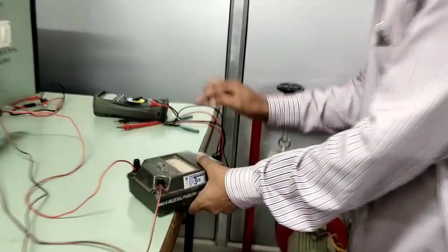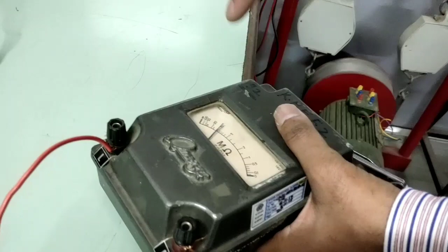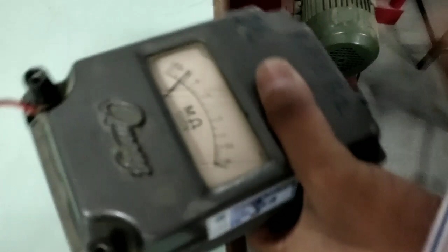Now I will move this handle and accordingly voltage will be generated in the Megger and it will show the reading of insulation of the cable. Okay, I am moving this spindle. Okay, you can see here some voltage is generated, some reading is shown, an insulation resistance value we are getting. Okay, can you see this? I am moving this spindle at the rated speed as per the requirement of the Megger. The Megger is showing some reading. It shows the insulation resistance of the cable.